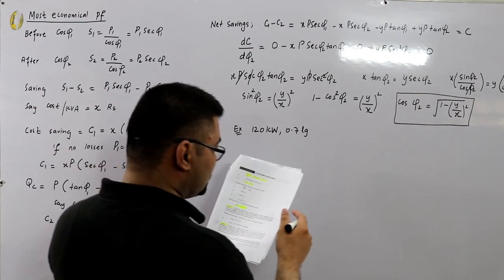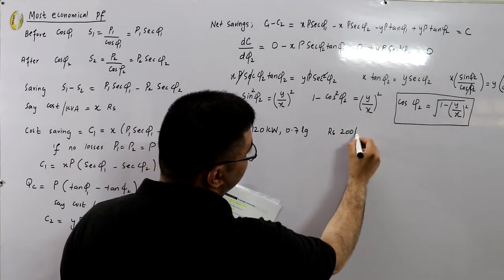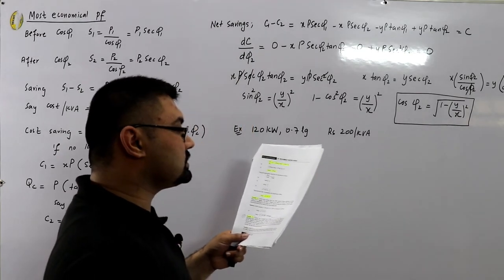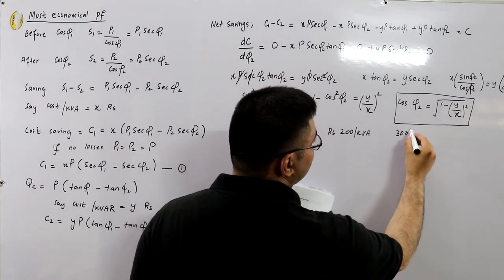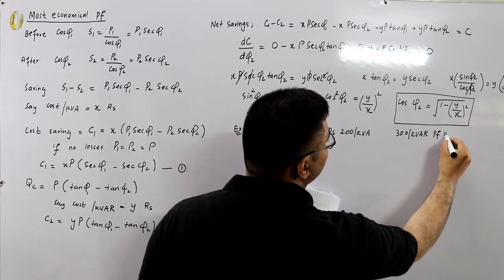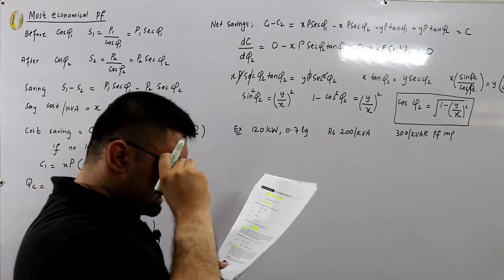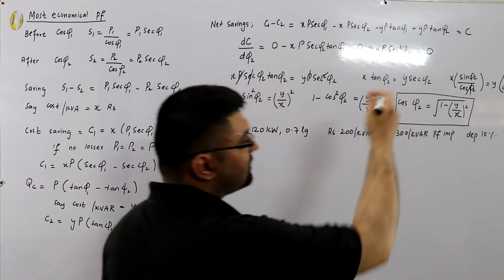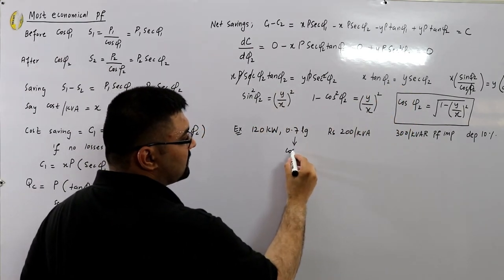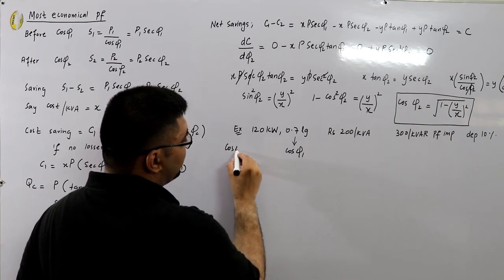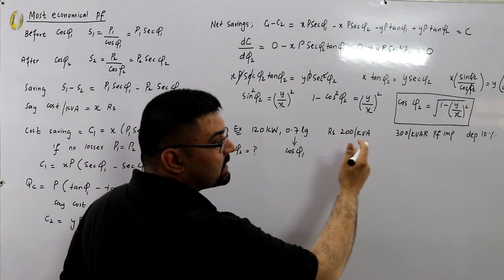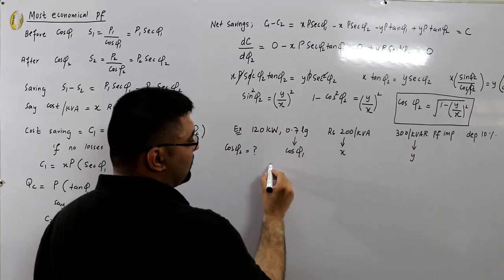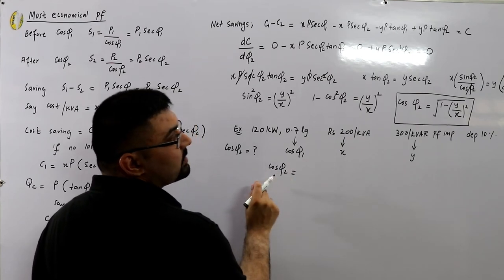The plant is charged Rs. 200 per kVA per annum — this is X. The power factor correction equipment costs Rs. 300 per kVAr, depreciated by 10%, so Y = 300 × 0.1 = 30 per kVAr per annum. Plugging into the formula: cos(φ2) = √[1 − (30/200)²].